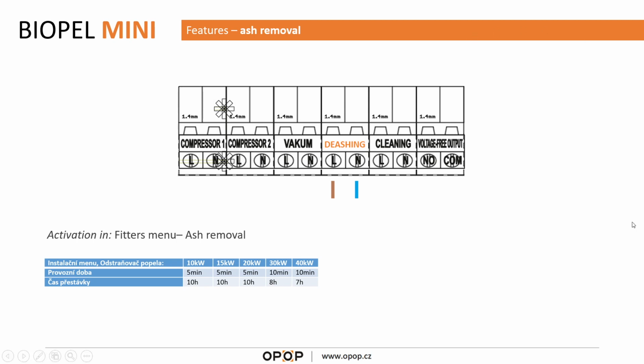Connection is simple. Inside the control unit you have output called de-ashing, and then again inside the fitters menu you have a function called ash removal system, and the setup which is done in factory is also really simple. There is an operational time, usually 5 or 10 minutes, and then there is a waiting time, 10 hours, or, you know, with bigger powers you have a little bit shorter waiting time till the ash removal system is again activated. So it works on timer basis or in intervals to remove the ashes from the boiler.